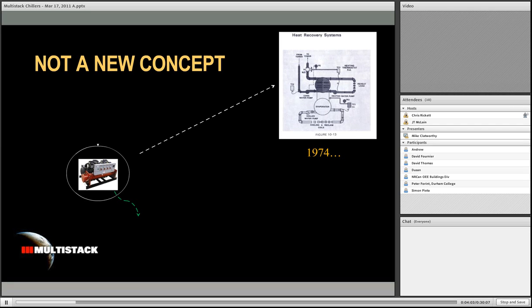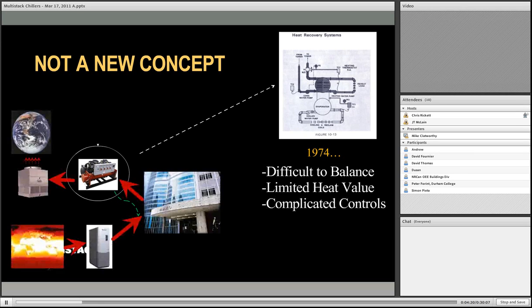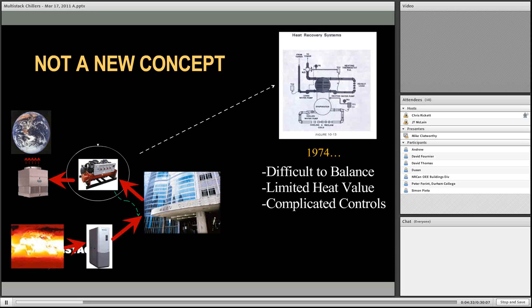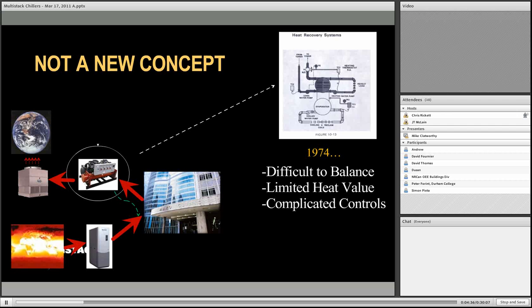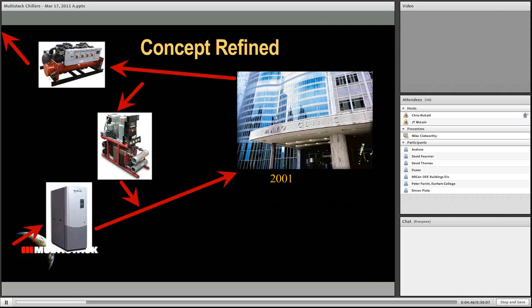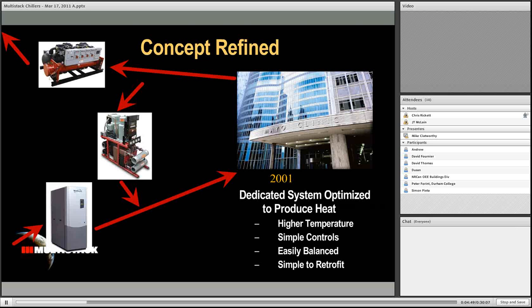The way that we do it is with something that is not new. It's called heat recovery. And the last time that heat recovery came upon the scene was back in the 70s at the time of the oil embargoes. Energy costs went up, and there was a lot of emphasis placed on finding alternative energy sources, not for environmental reasons, but mostly because the price of crude oil had gone sky high. But those systems, while they did exist, were difficult to balance. They had limited heat value. The controls were complicated. And what it boiled down to is when I need the heat most, I can't get it. So we're going to refine the concept.